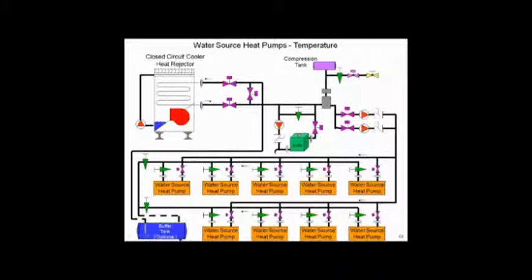So what are you getting at? I'm saying to you that a lot of these water source heat pump jobs out there that are 5 or 10 years old do not have condensing boilers, and they got maintenance problems. They got maintenance problems because you're raining in them, because the return water temps are getting below the 130 and you're tearing them up. I'm telling you, every water source heat pump job you know of should be changed over to condensing boilers immediately. Why?